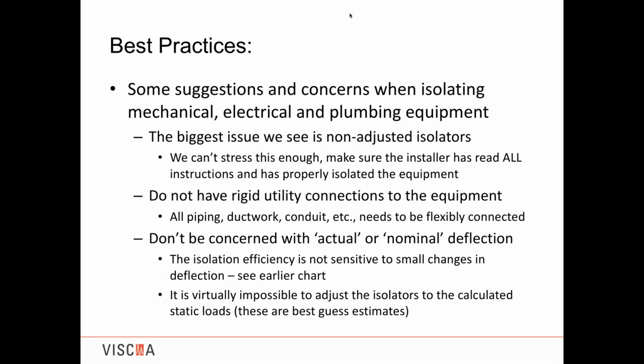So the flexible connectors on everything, especially conduit coming up from the slab underneath, going into your equipment that's running the electrical wire or a gas line, they have to be flexibly connected. You're just going to completely short circuit the isolation. And as I mentioned, we always ask for pictures. Once the pictures are taken, we typically see it.